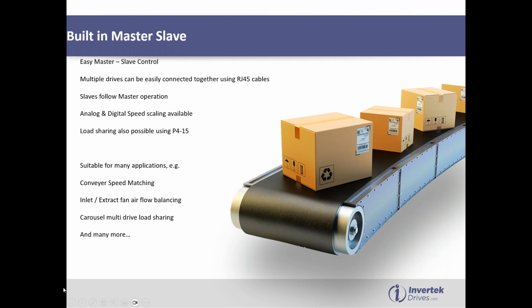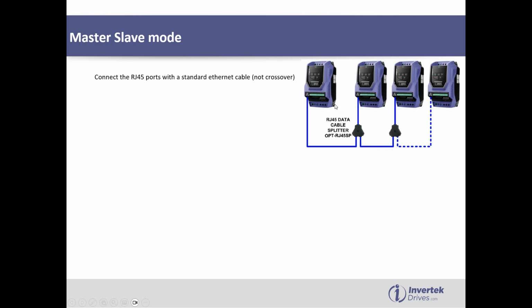With the master slave control, you can also do inlet and extractor fan airflow balancing very nice and easily. So you don't need to use external controllers for that. So carousel type applications where you have multiple motors working together. In master slave mode, it's very simple. We just connect the drives together. We use splitters for the RJ45 cables, but they're just standard RJ45 cables.